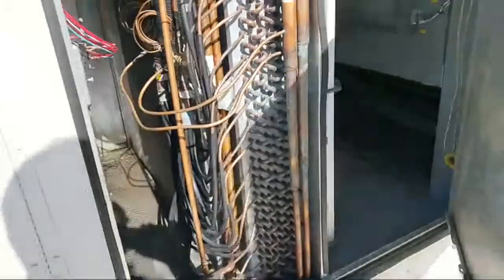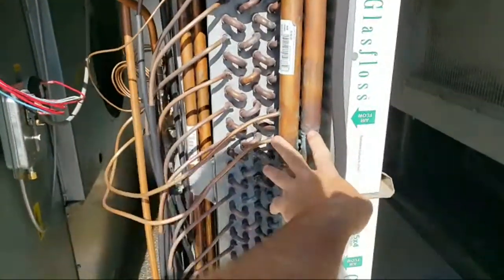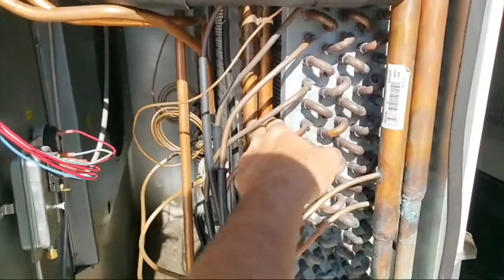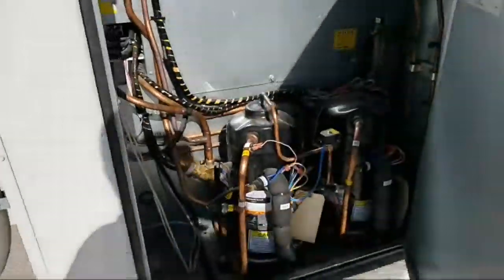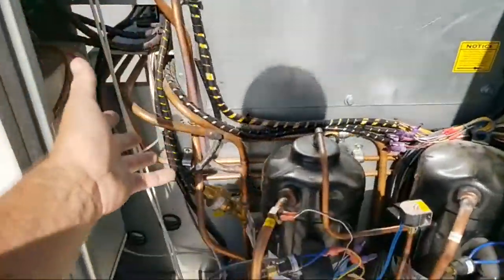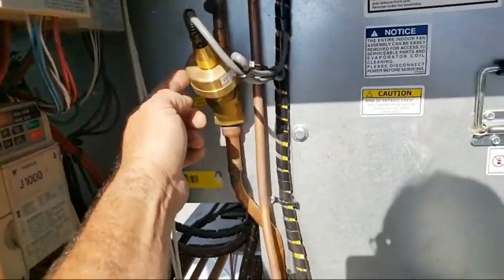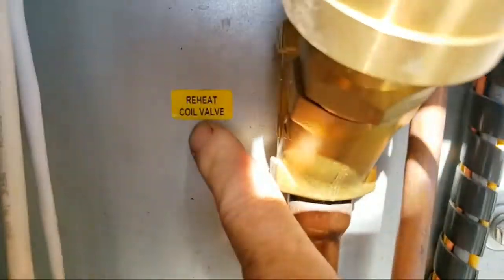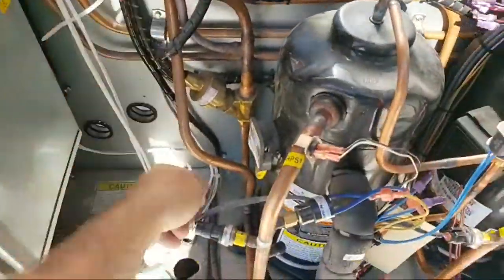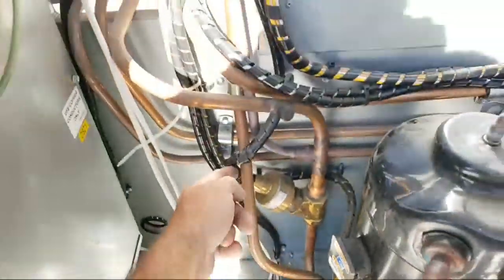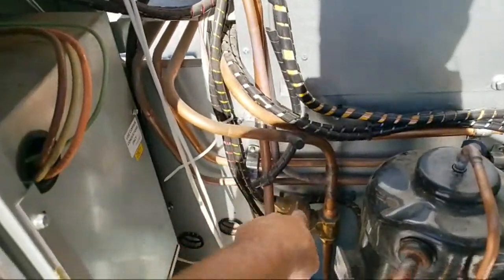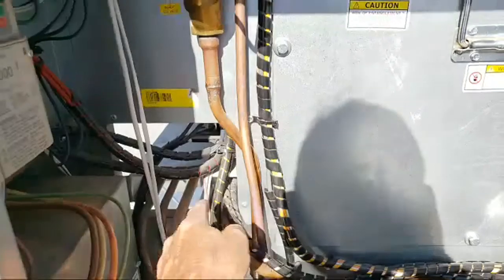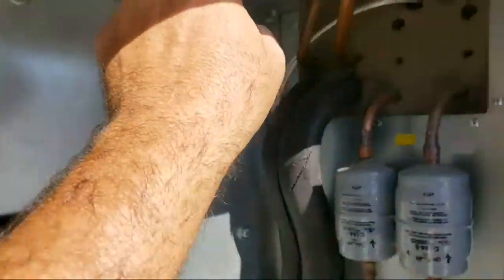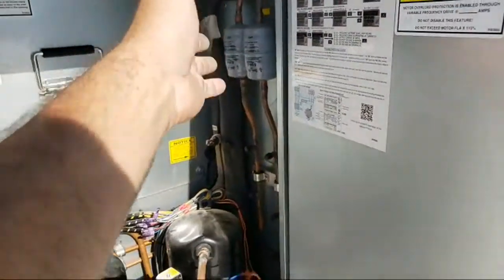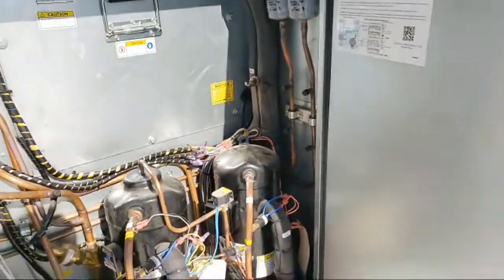And you have the two circuits, and then you have this coil right here, a reheat coil, where hot gas can be sent over after the evaporator in the airstream for dehumidification, which is awesome. So it just opens like a valve. So it's this hot gas. It'll be this valve right here, this hot gas valve, reheat coil valve. It comes from tees into the hot gas. It leaves the compressor, tees in. This valve will lower the proportion of that hot gas that goes to the outer coil, and instead this one will start opening at the same time and let heat go boom. So you're using basically a condenser coil right after an evaporator coil, instant dehumidifier.